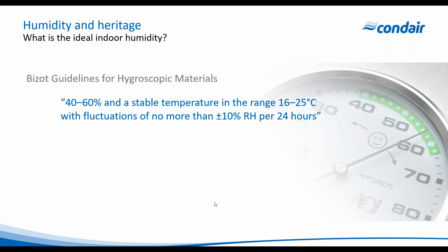So over the years, different conservation organisations have researched, developed and published guidelines on how the environment inside museums and galleries should be maintained. And as I briefly mentioned, the general consensus currently is that 40 to 60% RH is the current optimal condition. But also variance is important. The indoor humidity should not drift up and down by more than 10% RH in any 24 hours.